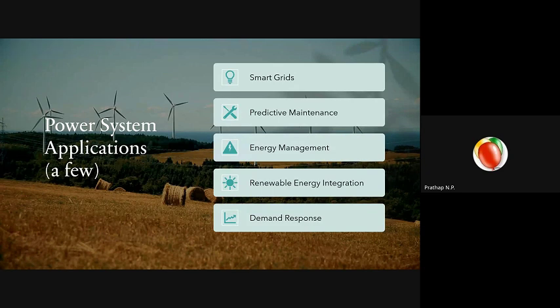So it is such a huge place, and that place gets 3 different utility incoming sources, because it is that important to have electricity there. If one source fails, it transfers immediately, automatically to the next source. So such a huge place, and it has 33 feeders per bus. So 3 buses, so 99 feeders. So think about that. 3 incoming utilities, 3 giant transformers stepping it down, and then 3 main breakers each going to a single bus, and they're tied by 2 tie breakers, and every single bus has 33 feeders. There are so many loads there.